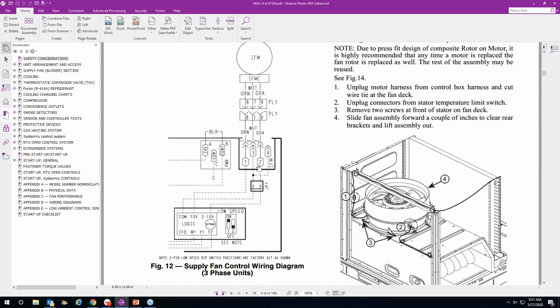If we look here on 2, your gray wire, that's your output. That's your speed reference output back to the motor. That's going to tell the motor how to run. So between gray and then white here, that's going to be your output reference signal. So how do we troubleshoot this thing? The indoor fan motor's not running. I know I've got a call for either continuous fan, I'm in the heating mode, I'm in the cooling mode, whichever, but the fan isn't running.